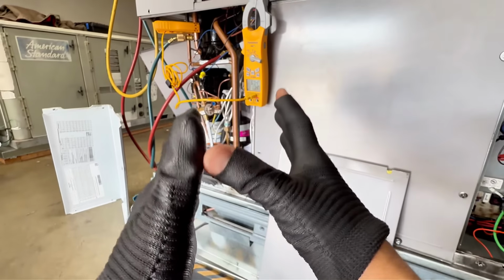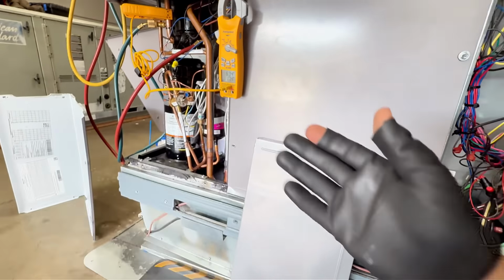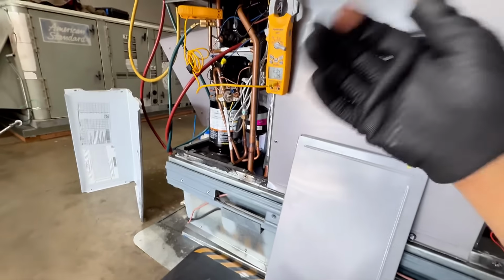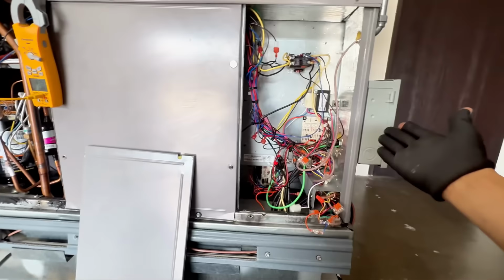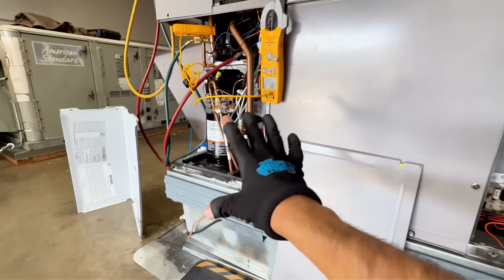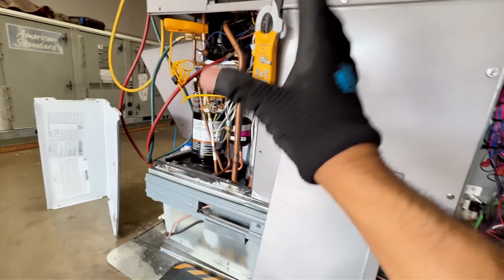Yeah. But typically, when checking components that are high voltage, you're going to do it with the power off, check the compressor, ohm it out. But I would only do that if my breaker tripped or my fuses went bad because it pulled too many amps. I'm not going to do that right away. You're going to do what's easy first.